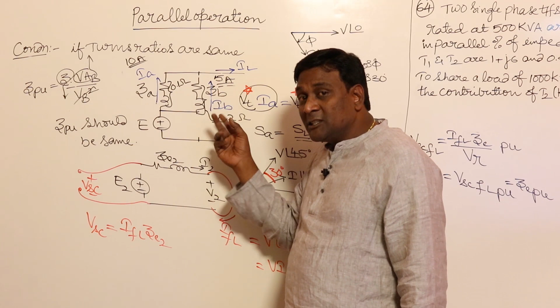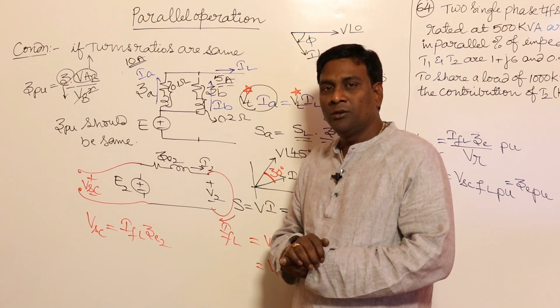In order to attain this condition, what is the condition? If it is 10 kVA and if it is 5 kVA, the total combination should give you 15 kVA. In order to attain that, the short circuit voltage of this to circulate full load current and of this to circulate full load current should be the same, or ZE per unit with respect to its own kVA rating of 10 kVA, and ZE per unit with respect to its own kVA rating of 5 kVA, should be the same.